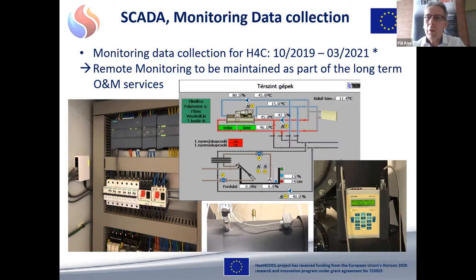This system, as I mentioned, is 1.7 megawatt. Our client is the municipality. They want to upsize it to 4 megawatts, so further development is possible. And of course, we need a lot of wastewater flow. Here for 1 megawatt, we use around 3,500 cubic meters per day of flow to have one megawatt of heating and cooling for our end users. So that was all about the Budapest site.